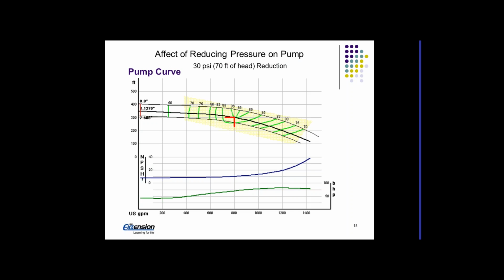So how does it affect our pumping? Here we have this one set up for 800 gallons a minute at 300 feet of head. The question is, what happens if I reduce the pressure by 30 psi, or 70 feet of head? Well, that's going to drop my pressure, and if I do nothing to the pump, it's going to now operate over here. So that's going to operate at about 1,100 gallons per minute. So this poses some issues.